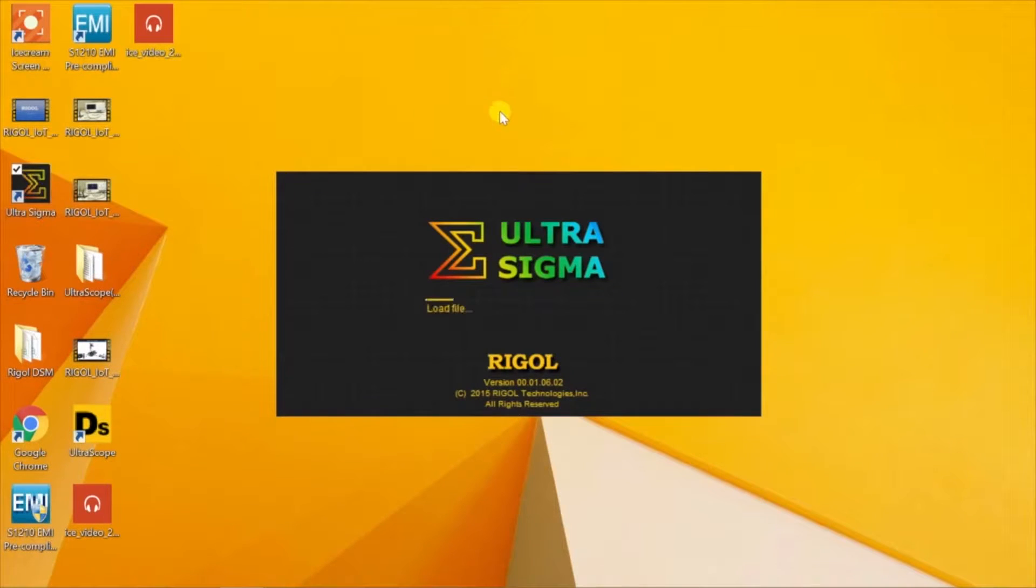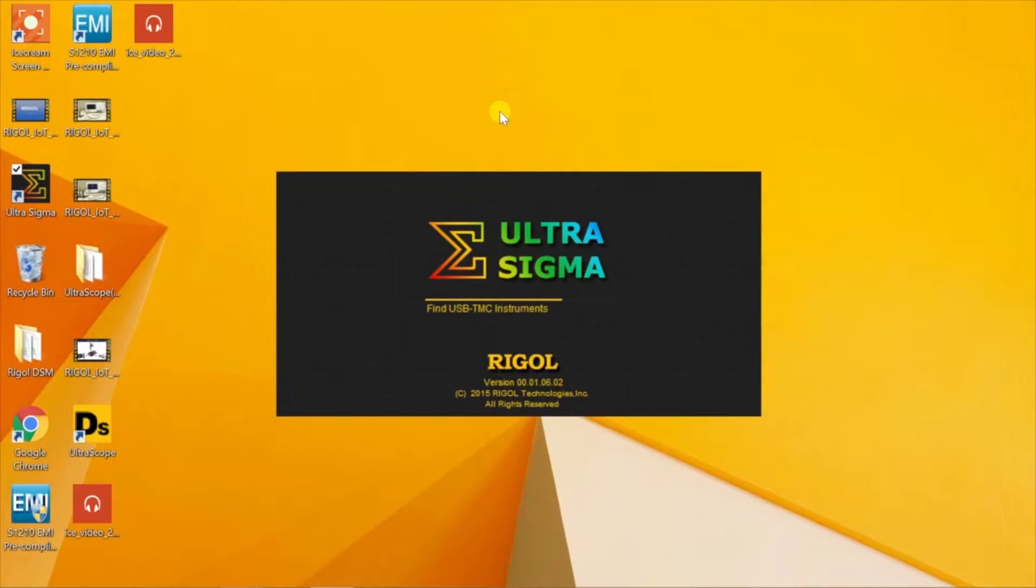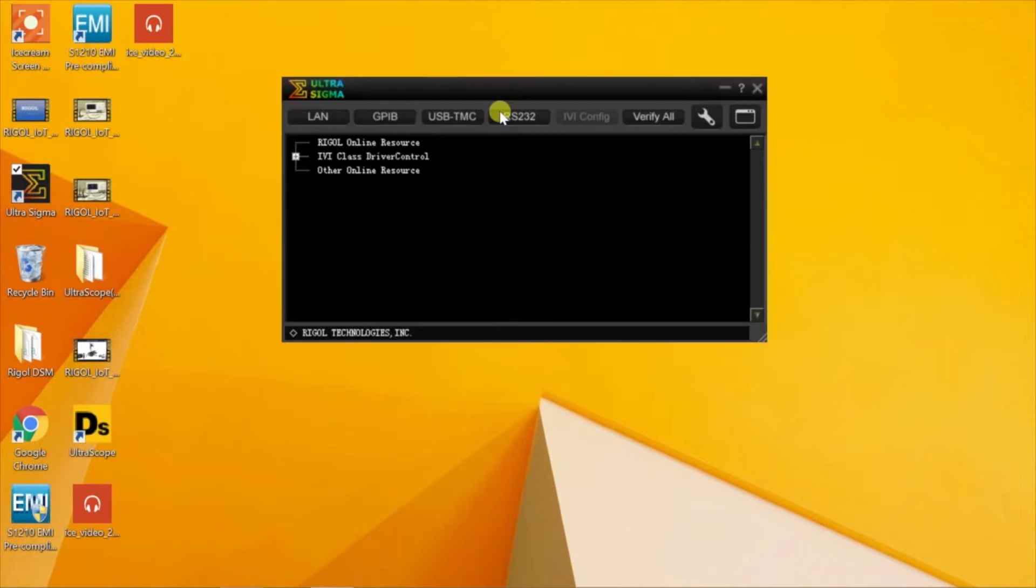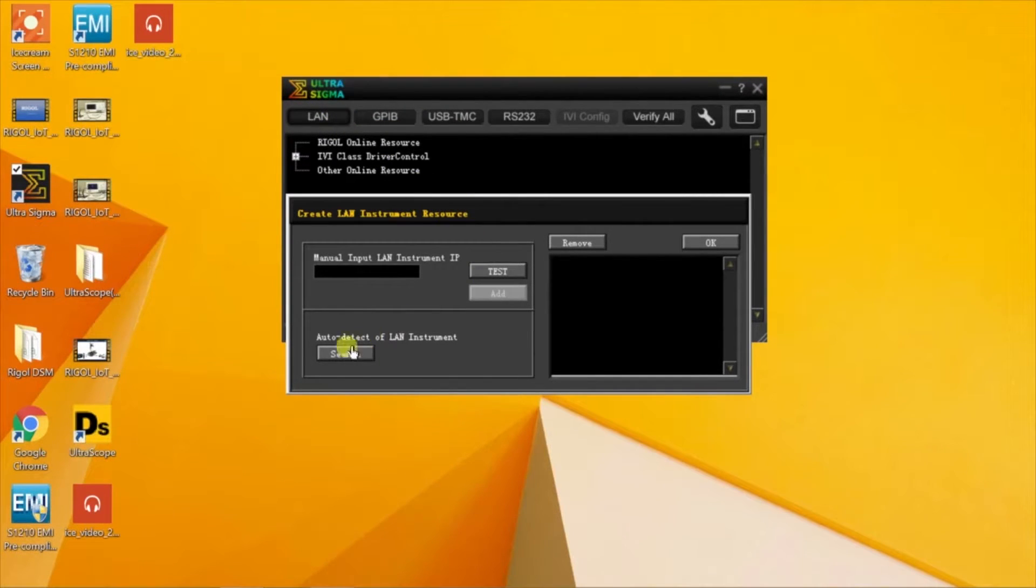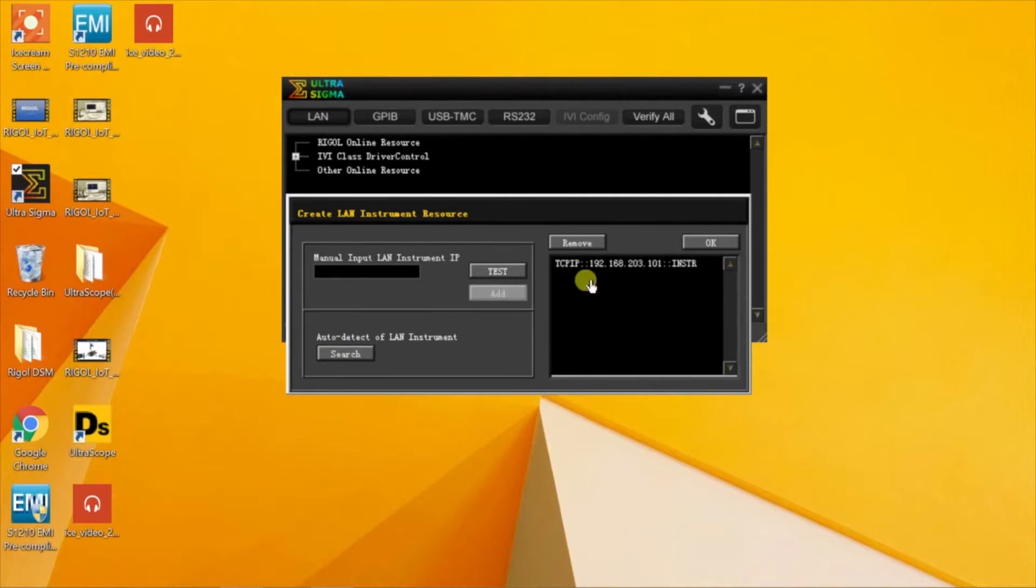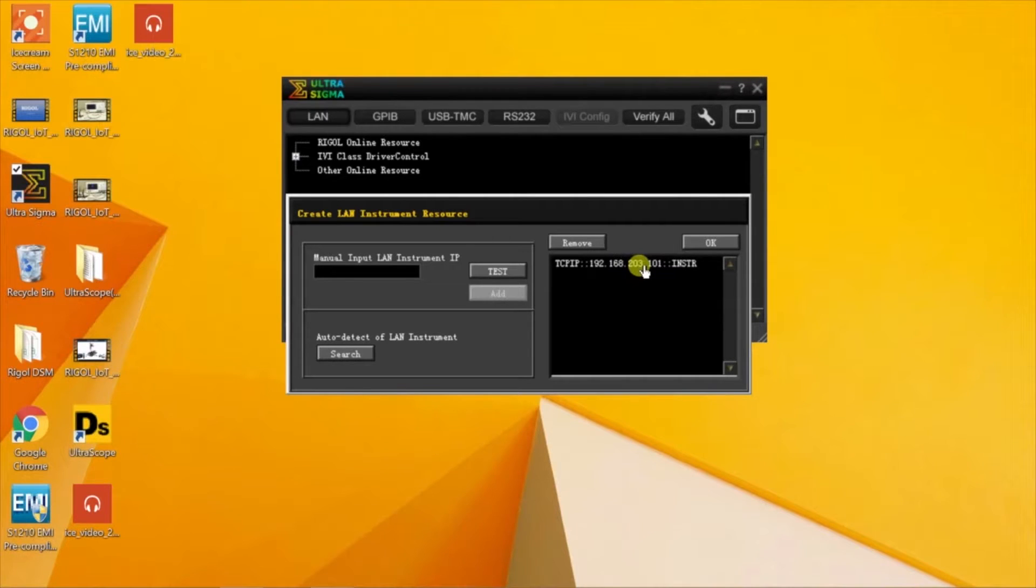After starting Ultra Sigma, we then click on the LAN button. And here we can use the Auto Detect to see if we can find our LAN instrument. There we've identified the same scope at 192.168.203.101.